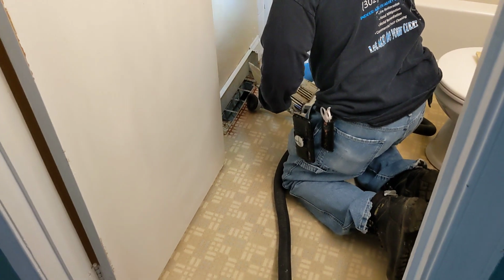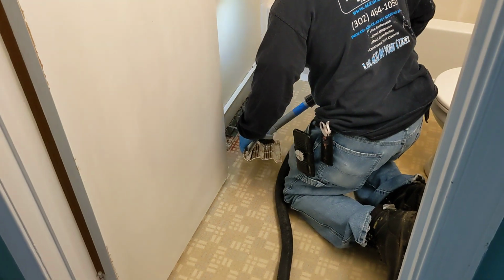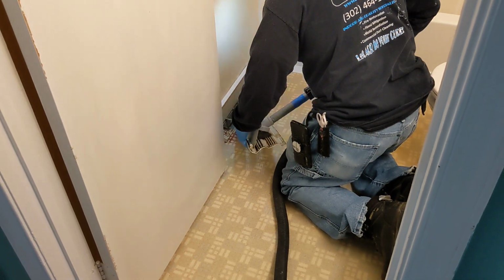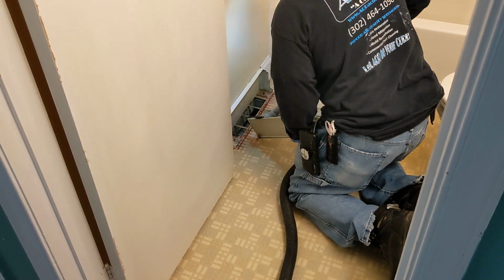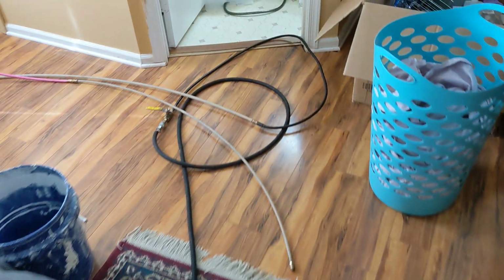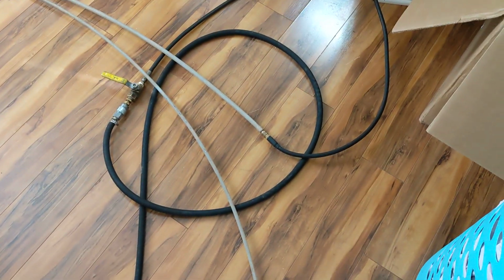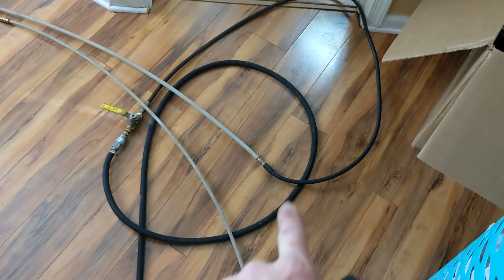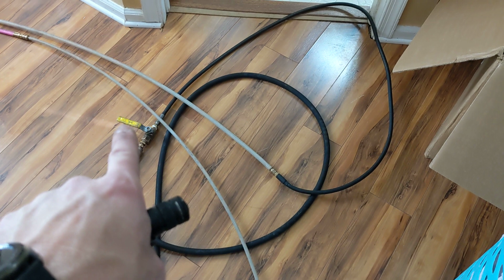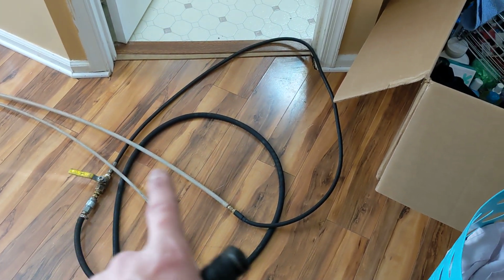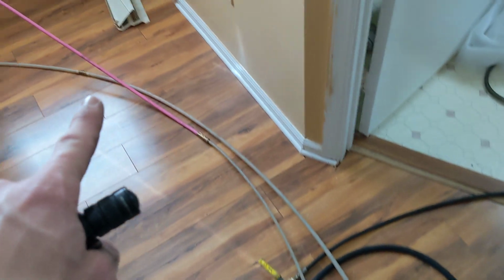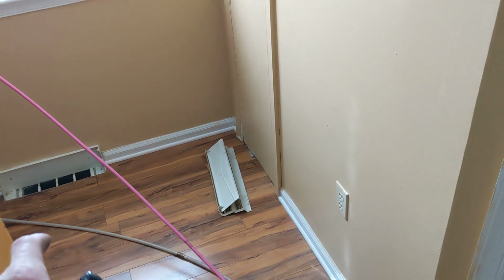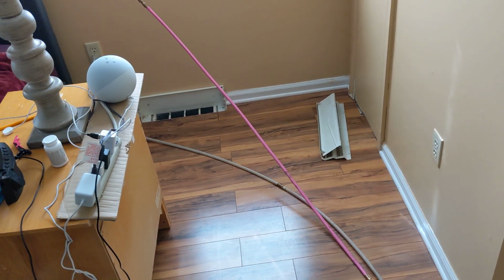And then once he's done with that, we start the whip system, it's called. That utilizes a HEPA collector that we showed earlier in the video, an air compressor with a whip system, which is this setup here. So the air compressor supplies air through this black hose to a trigger. The trigger just opens and closes, allowing compressed air to come through. It then goes through these tubes that we send through the ductwork. Again, starting from the farthest point away from the unit, working our way back. And then on the end of these tubes will be whip tips, they're called.